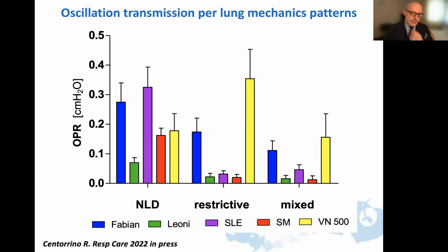It's been published like 25 years ago for the first time, and is calculated as the ratio between the oscillatory pressure measured at the given level, for example, at our lung model in our case, divided by the oscillation that has been set on the ventilator. So the OPR is giving you the idea of a portion, the fraction of the oscillation that is actually transmitted downstream compared to the oscillation that you asked the machine to provide. Because, you know, this can be reduced by the compliance of the tubings and the model in this case, and the airways and the lung.